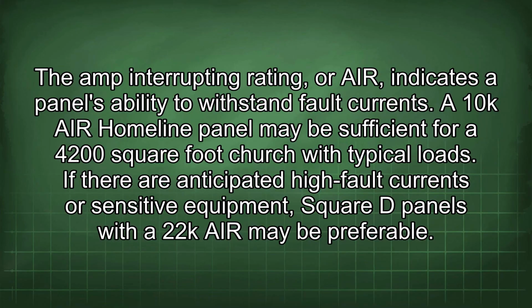Amp interrupting rating, or AIR, indicates a panel's ability to withstand fault currents. A 10k AIR Homeline panel may be sufficient for a 4,200 square foot church with typical loads. If there are anticipated high fault currents or sensitive equipment, Square D panels with a 22k AIR may be preferable.